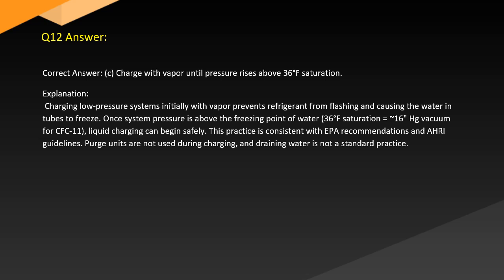Answer. Correct answer. C. Charge with vapor until pressure rises above 36 degrees saturation. Explanation. Charging low-pressure systems initially with vapor prevents refrigerant from flashing and causing the water in tubes to freeze. Once system pressure is above the freezing point of water, 36 degrees saturation equals 16 inches Hg vacuum for CFC-11, liquid charging can begin safely. This practice is consistent with EPA recommendations and AHRI guidelines. Purge units are not used during charging, and draining water is not standard practice.